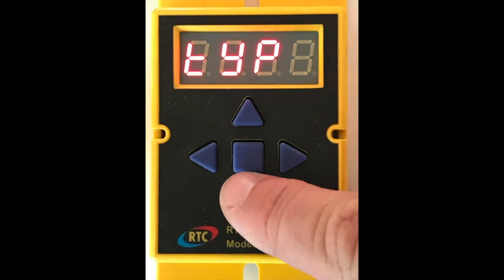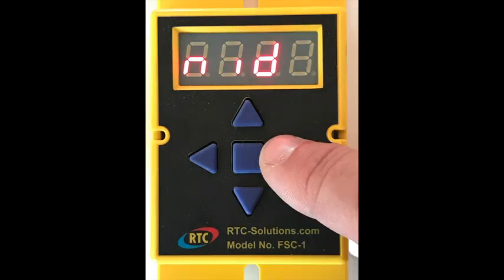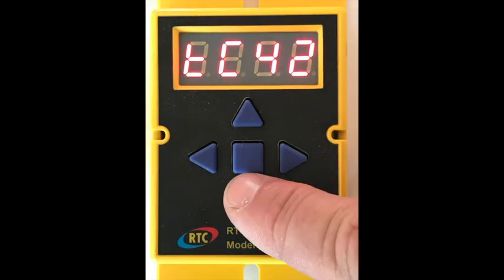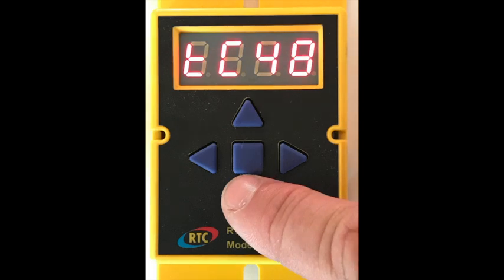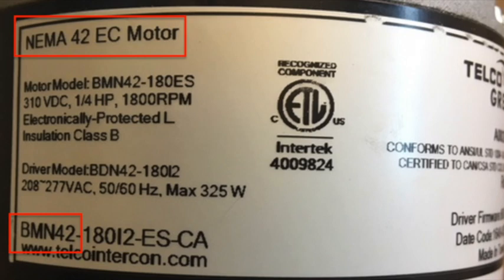The next menu is TYP, or type. This tells the controller what brand and type of motor you're trying to control. Your options here are NID for NIDEC motors, or TC42 for a Telco model 42 motor, or TC48 for a model 48 motor. The Telco model numbers can be found on the motor label.